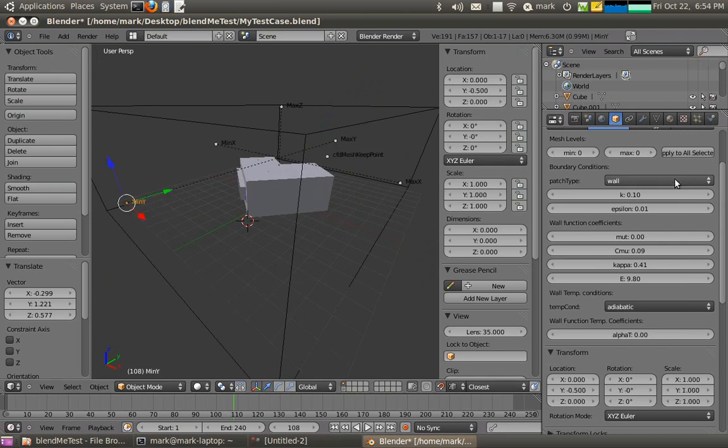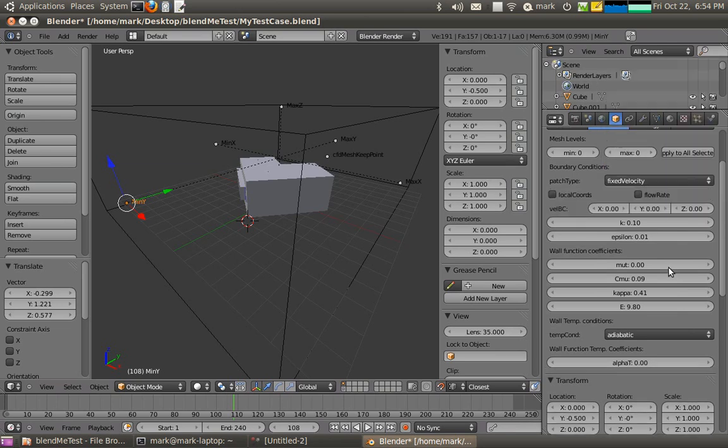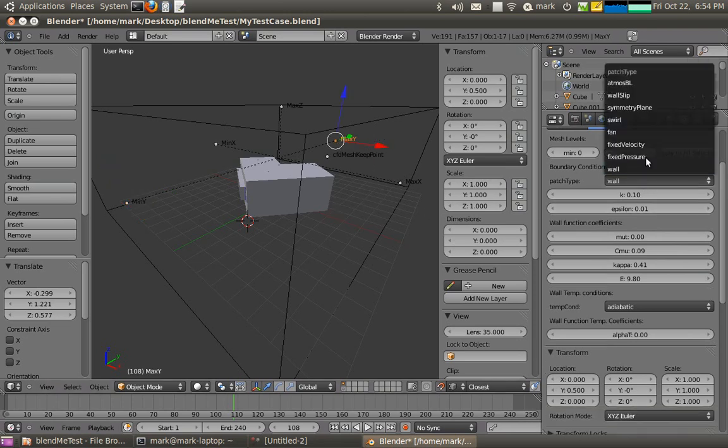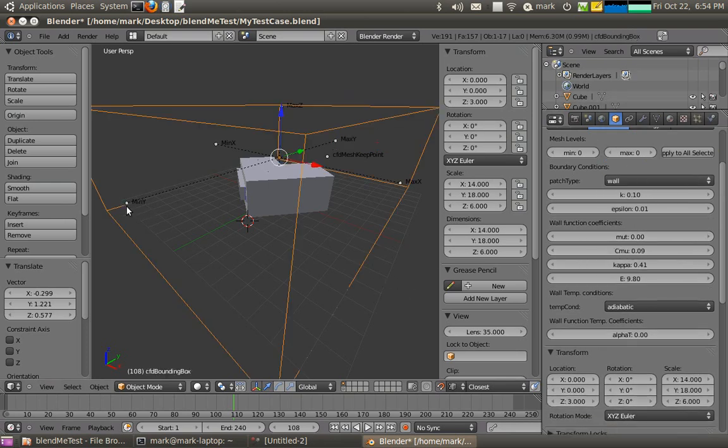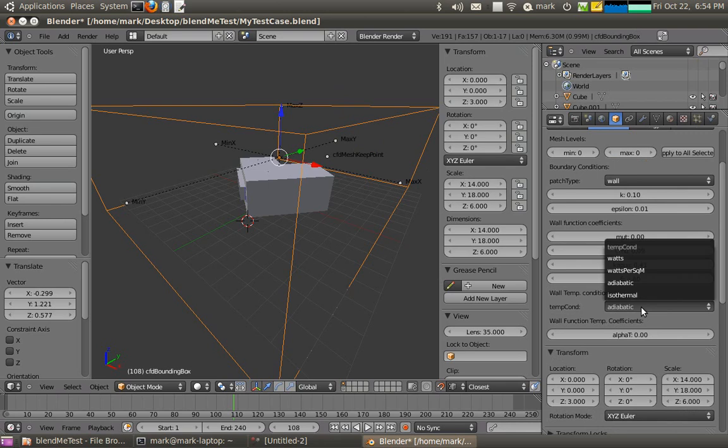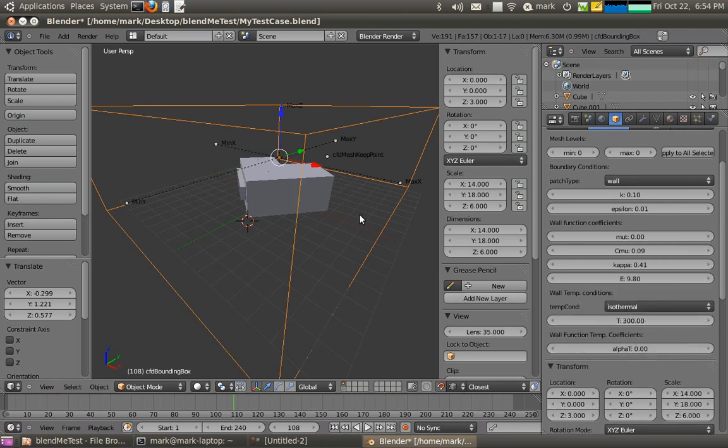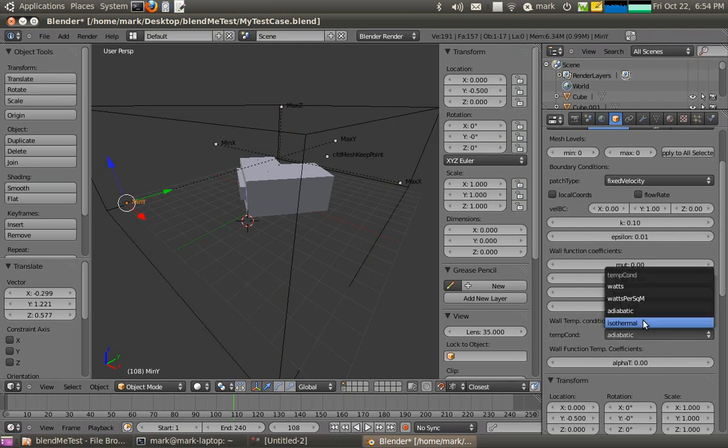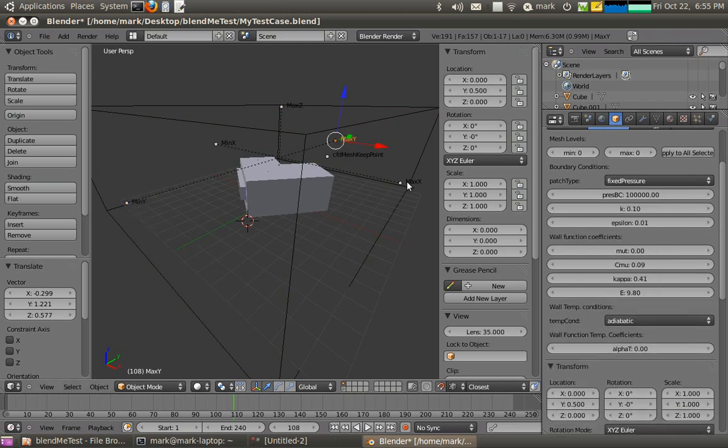Now we want to have some wind coming in to blow through the windows. So we go to the minimum Y coordinate and we'll set a fixed velocity of let's say 1 meter per second coming in. Now that air needs to go everywhere, all the air that we bring into the space needs to go somewhere. So we'll set it out through a fixed pressure outlet. The air coming in is just going to be coming in isothermally at 300 Kelvin.